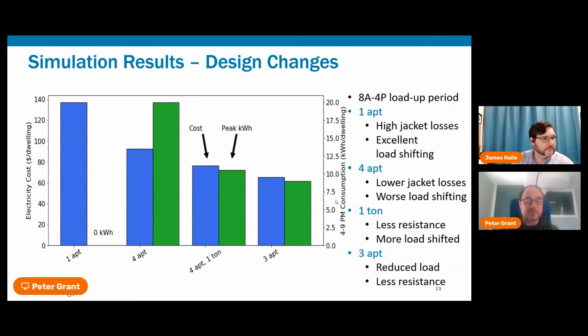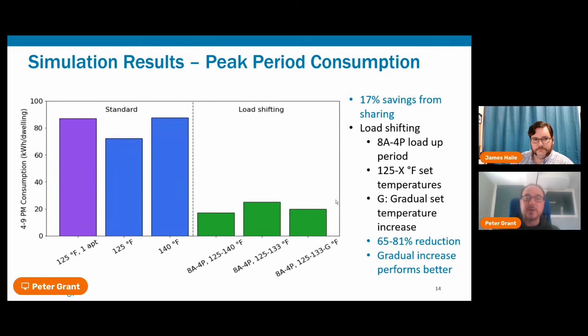There are lower jacket losses, so there's less heating required. Then when we start implementing the load shifting controls in the shared configuration, we see a 65 to 81% reduction in peak period electricity consumption. And this is what you would expect. You heat up the tank higher before the peak period starts. You don't need to heat as much during the peak period.